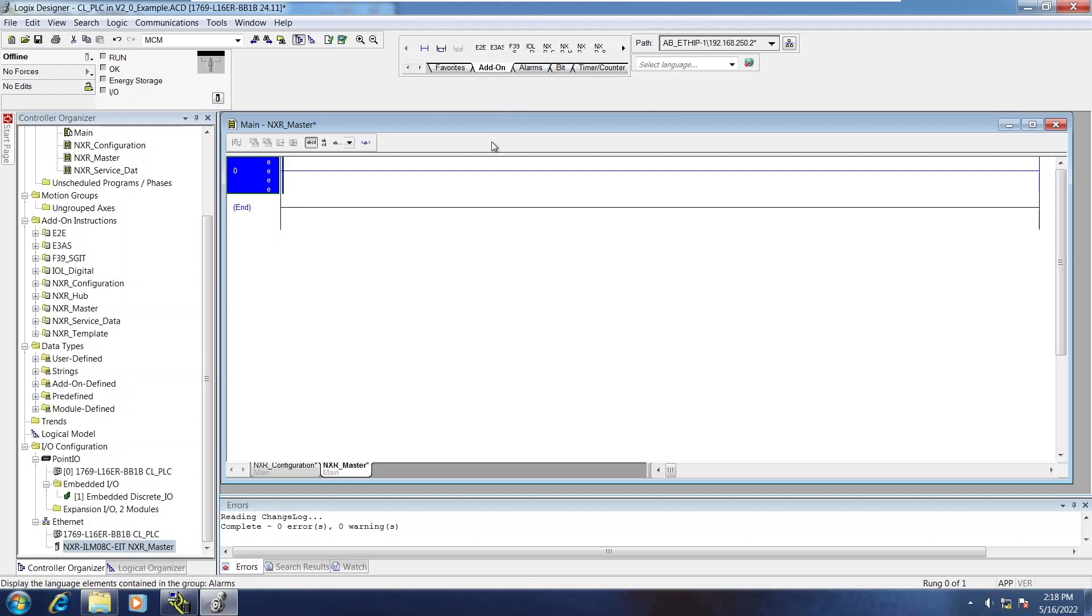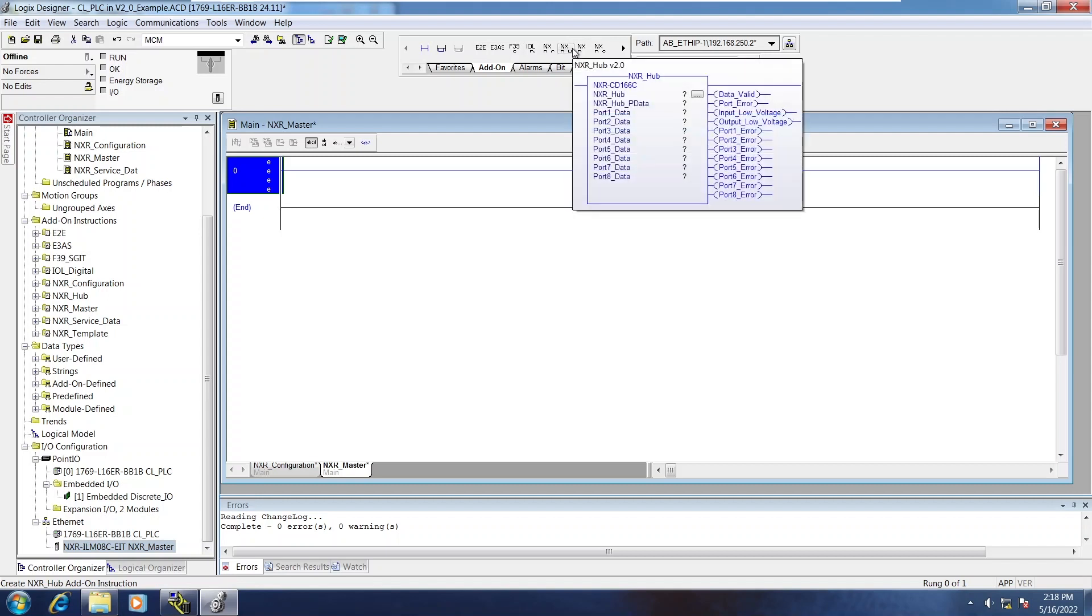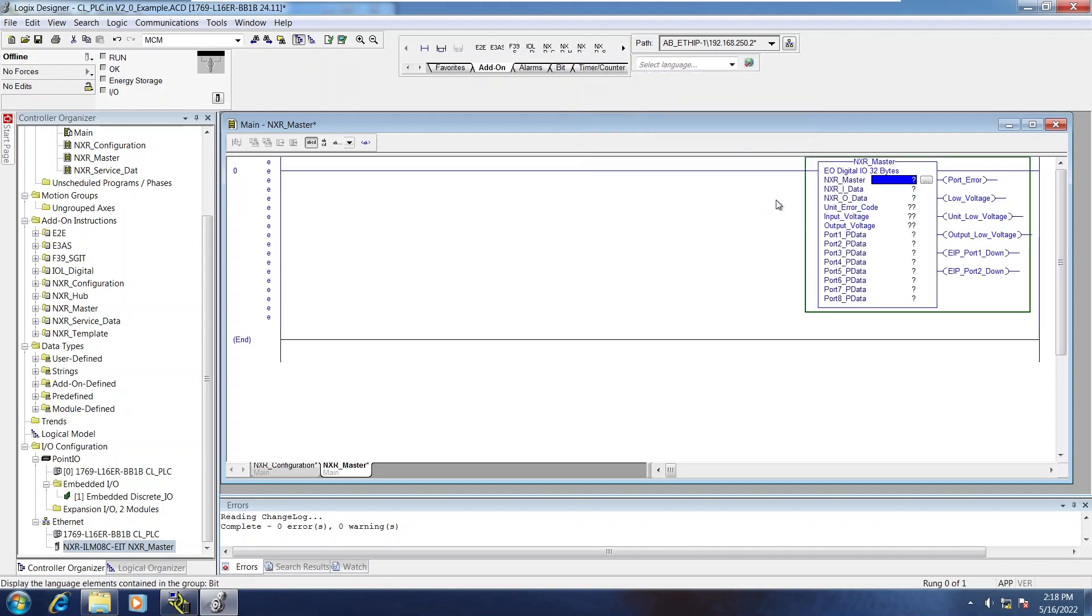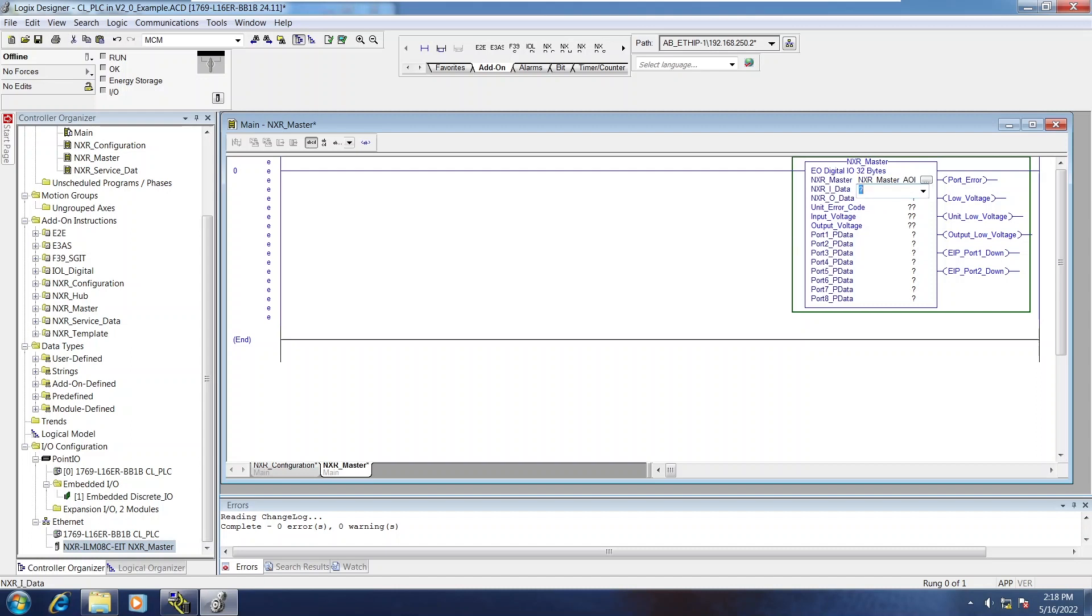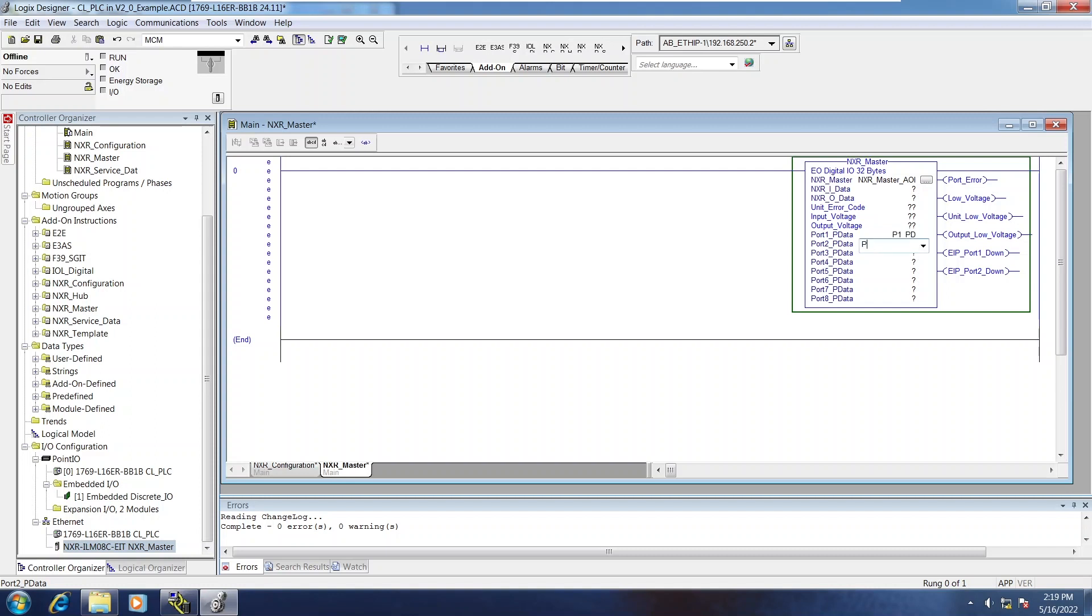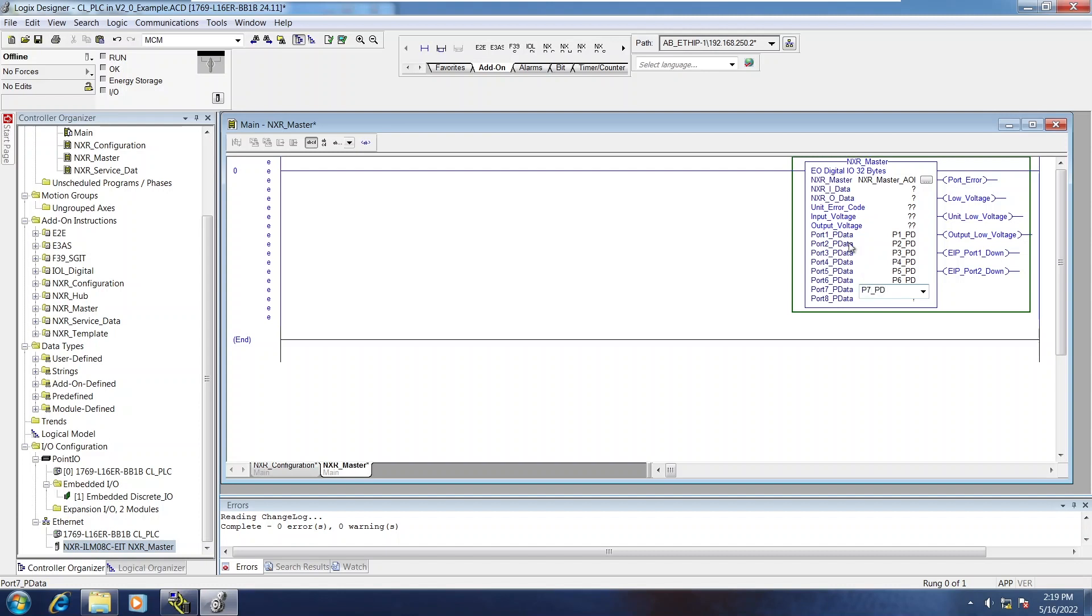Now, I'm going to put this on a rung by itself and a program by itself, but that's not how it needs to be set up. The first AOI is going to be the NXR master, and I'm just going to tag everything first. Not everything needs to be tagged. Only the AOI variable itself and then all of the process data or pData variables need tagging. Go ahead and create those variables now.